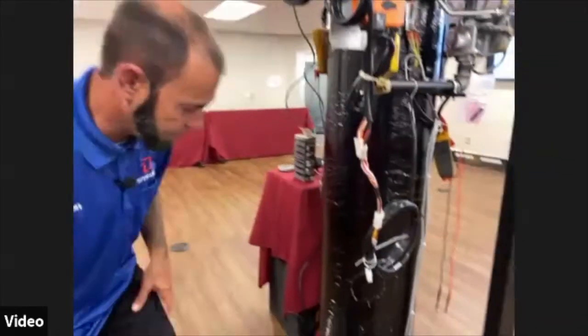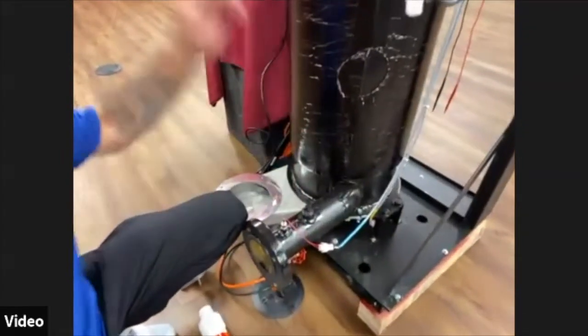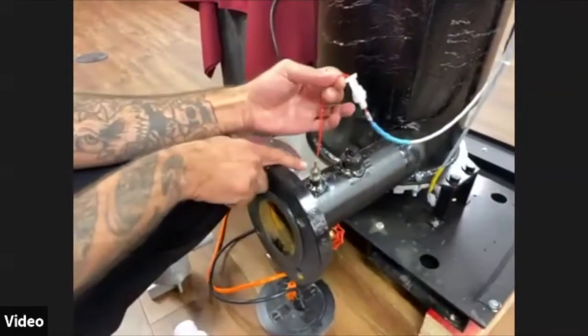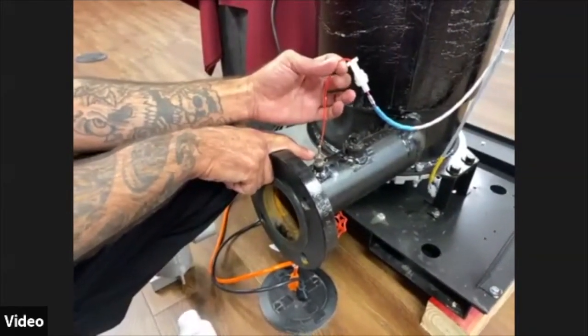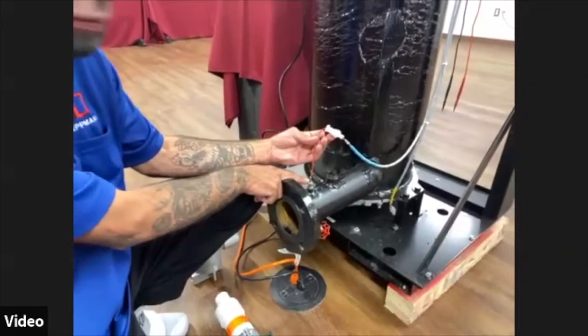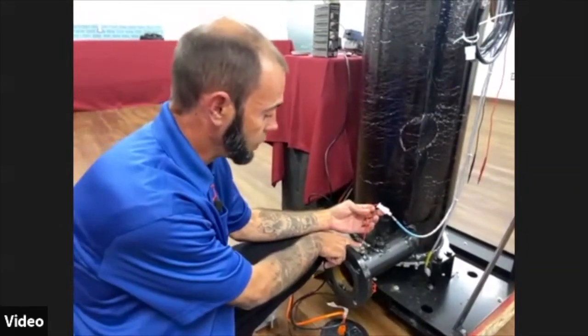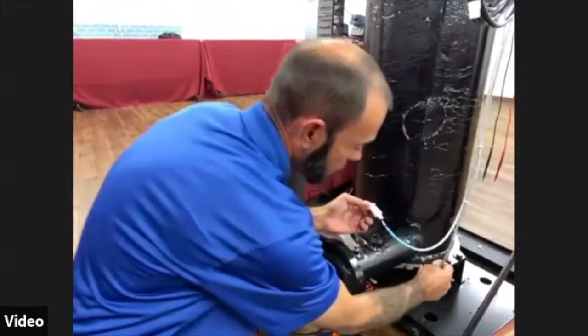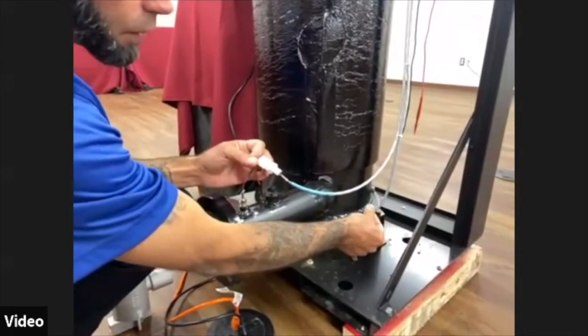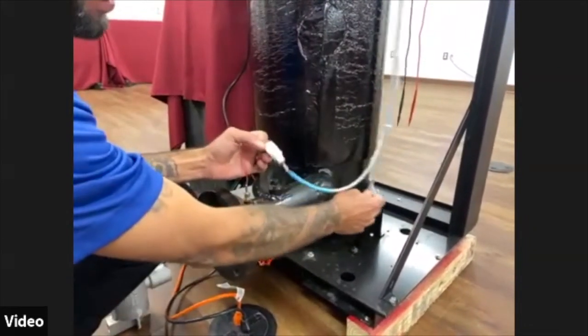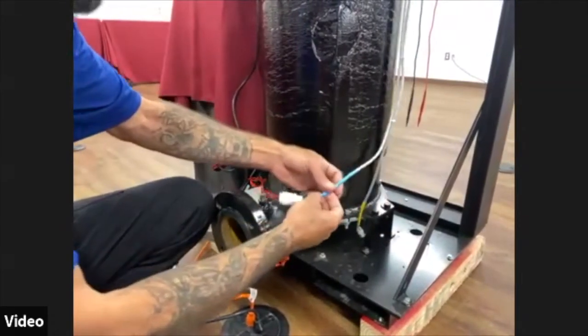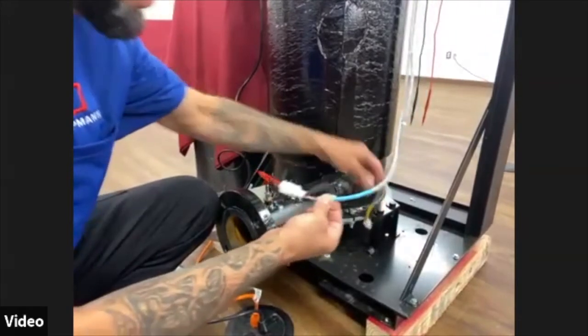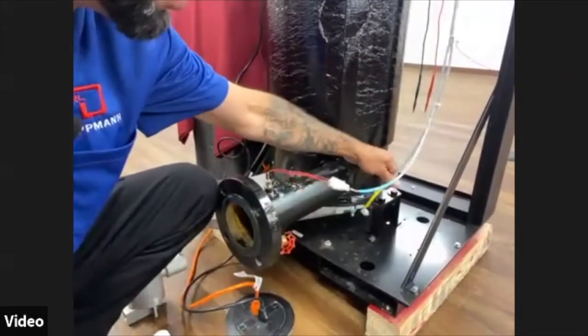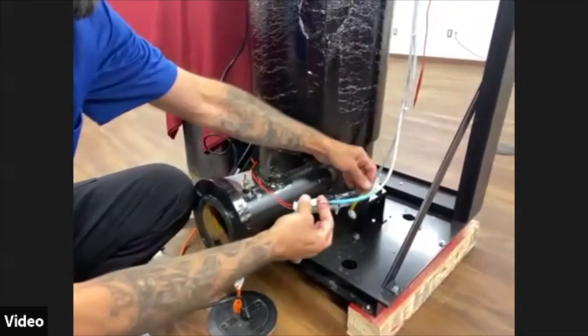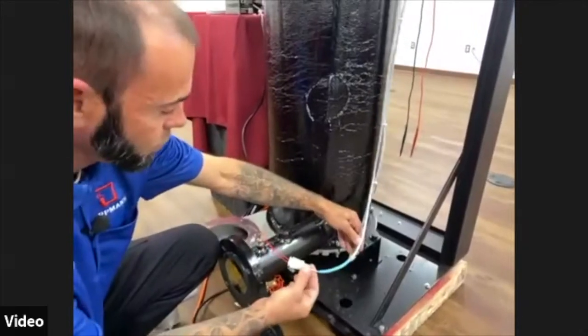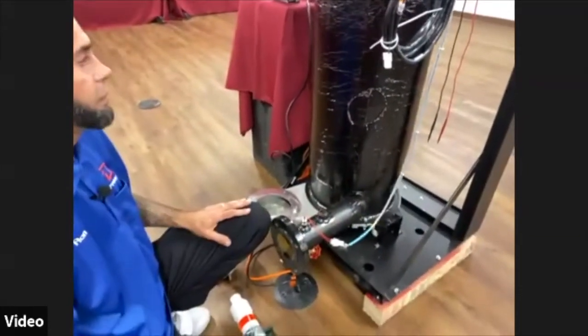Coming around to the back bottom side of the boiler, just like we had that supply sensor, you'll notice that looks pretty similar to our air sensor. Again, this won't replace the supply sensor because that's a dual temperature, but this can be used as a return sensor. It can be used as a flue temperature sensor, and or it can be used as the air temperature sensor on the air fuel valve. Remember we talked about the red coating. This is blue, this is yellow. Blue would be your cool water, so it's your return water. Yellow would be your exhaust. So if you ever happen to disconnect these and you're noticing temperatures don't look right, you may have reversed these. It's very easy to do if they're both disconnected.